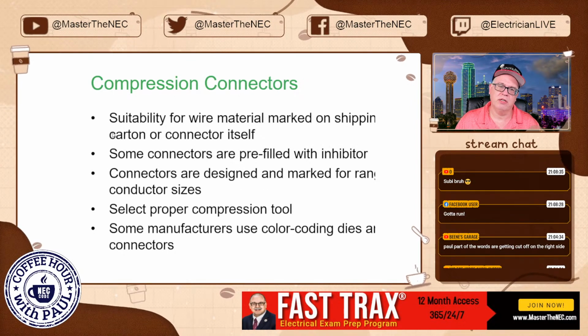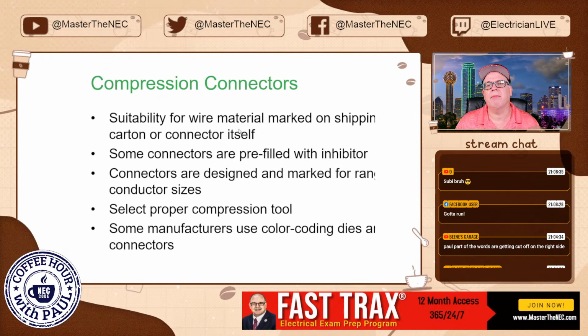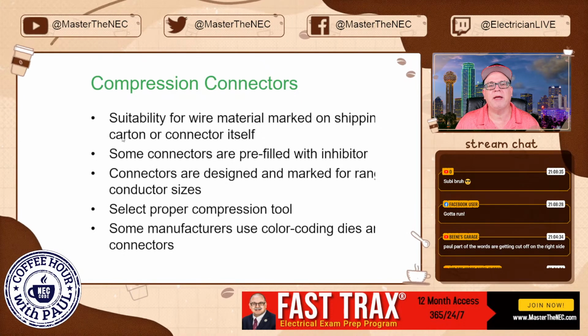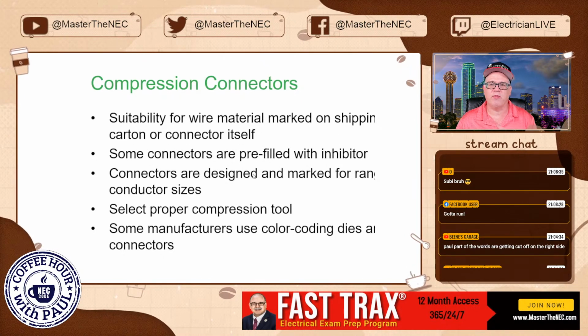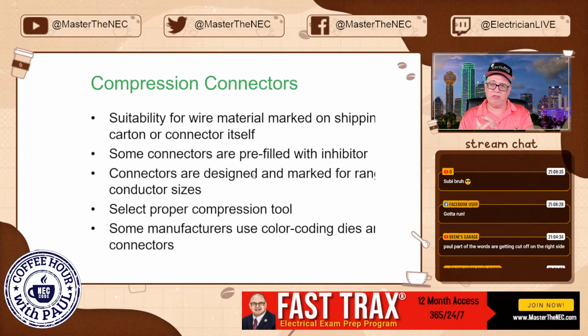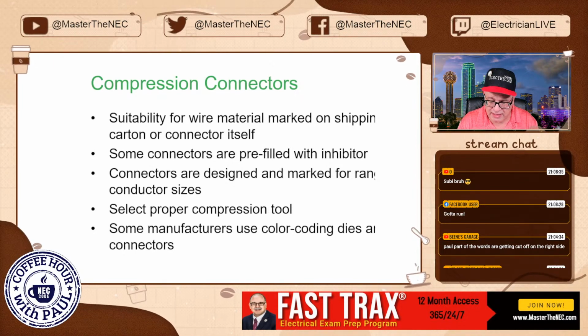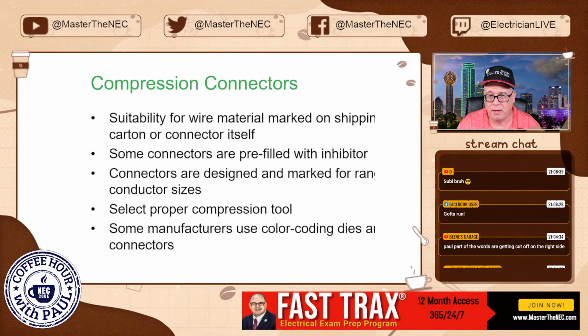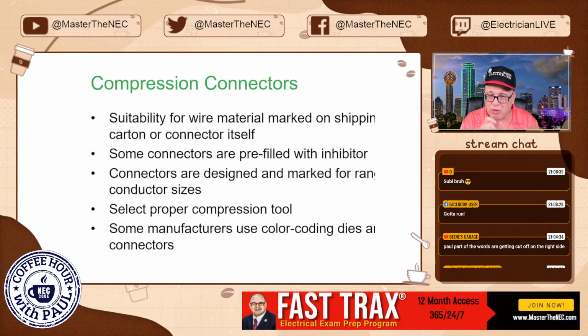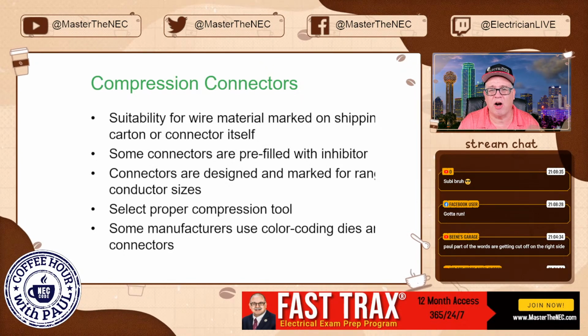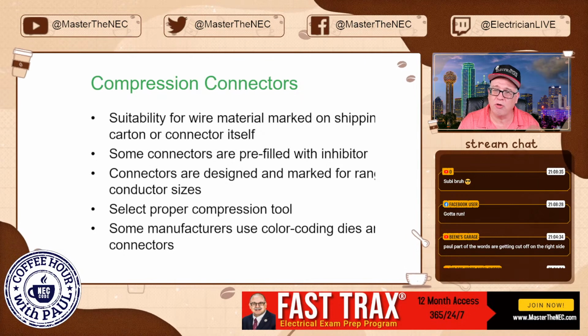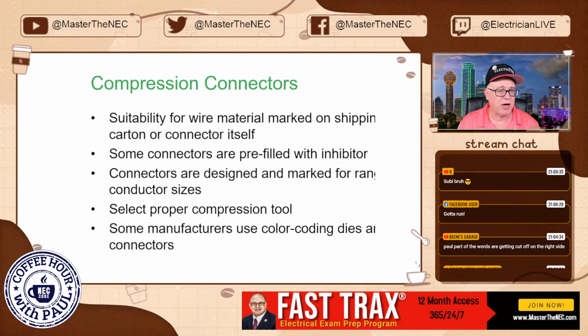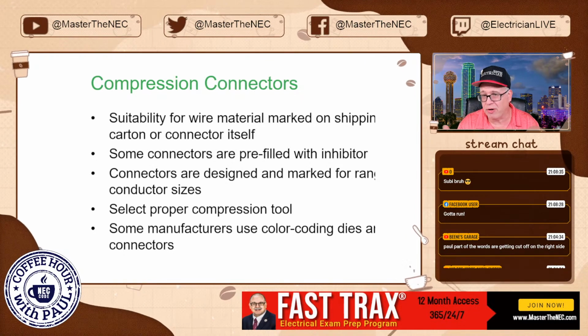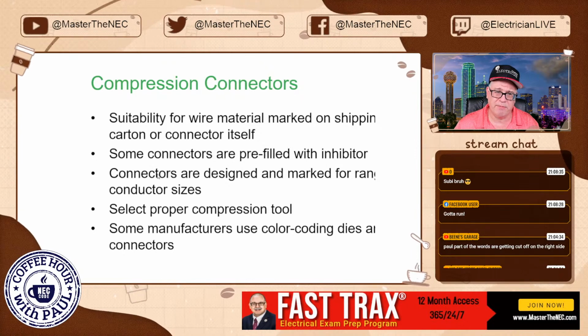Compression connectors. Suitable for wiring material marked on the shipping carton and connector itself. So if you've got compression connectors, you need to make sure you look at the packaging, because a lot of times these are small, little components, and you need to look at the carton and it'll tell you what it's used for, whether it's aluminum, whether it's good for copper clad aluminum, whether it's good for copper. All those things are going to be in the container.